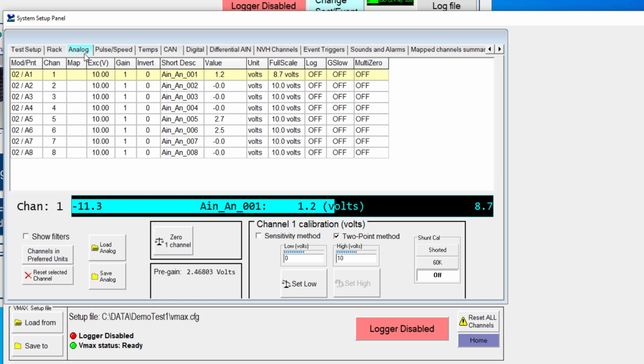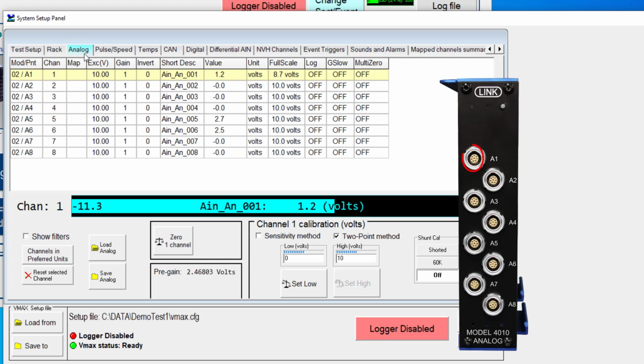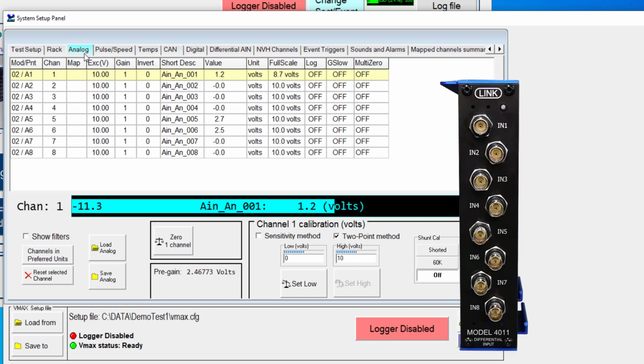The Model 4010 features 8-pin LEMO connectors and does have excitation capabilities up to 12 volts on our latest modules. We also have a Model 4011 that is a differential analog input module that does not supply any excitation voltage. So that would be used in a case where you have a sensor that is already being powered, perhaps on a vehicle or maybe in a laboratory test cell by some other device. And you just need to look at the differential voltage coming out of that sensor.